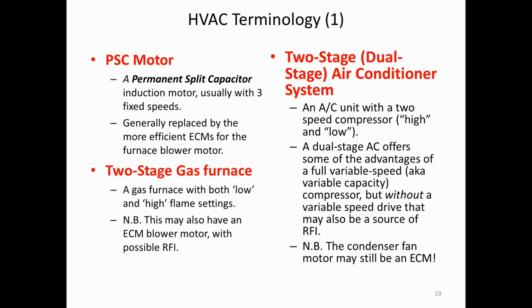Now, a 2-stage gas furnace is a gas furnace where you have both low and high flame settings. I have one. It's relatively efficient. But a 2-stage gas furnace may also have an ECM blower motor. So if somebody tells you this is a 2-stage gas furnace, and I guarantee it won't have any RFI, the question is, really? Does it not have an ECM blower motor based on the fan efficiency regulations of 2019? The salesman may lose the sale at that point, but that's the question you ask.